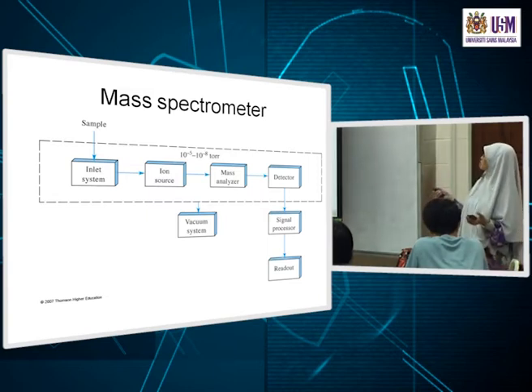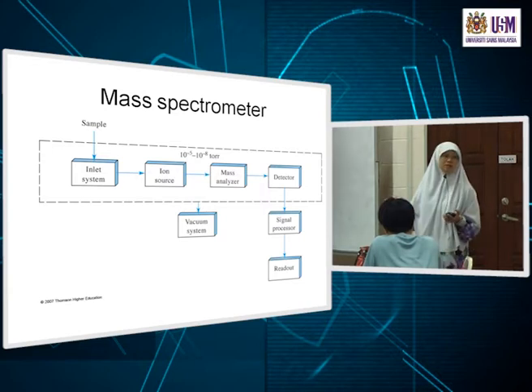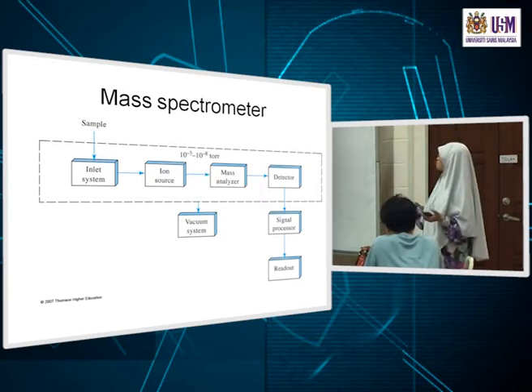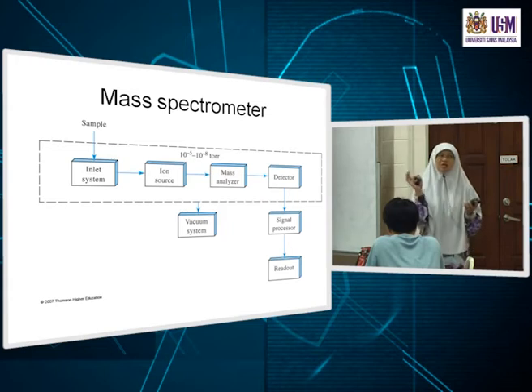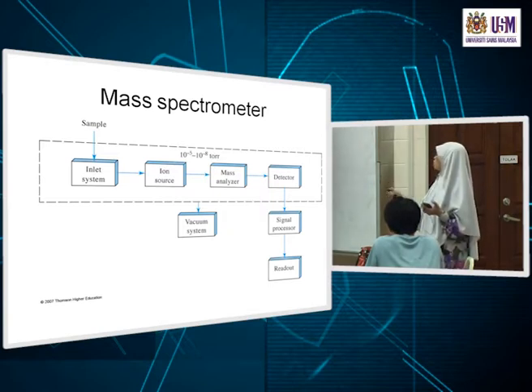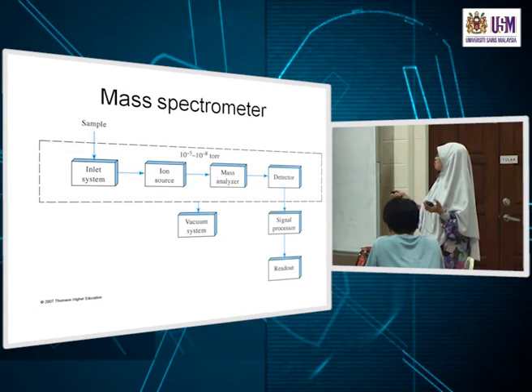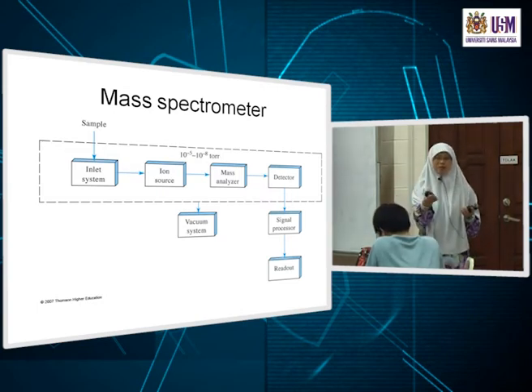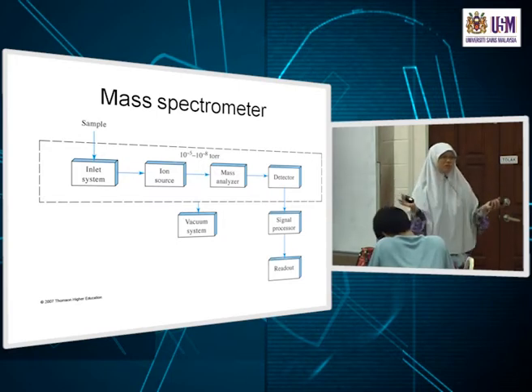The main components of a mass spectrometer: you must have an inlet system for how you introduce your sample, and if you notice it's all in a vacuum — low pressure — because you cannot have too many ions. It's going to be difficult to separate and detect them at high pressure. You're talking about pressures of 10⁻⁵ to 10⁻⁸ torr, not like AAS where the plasma works at atmospheric pressure.